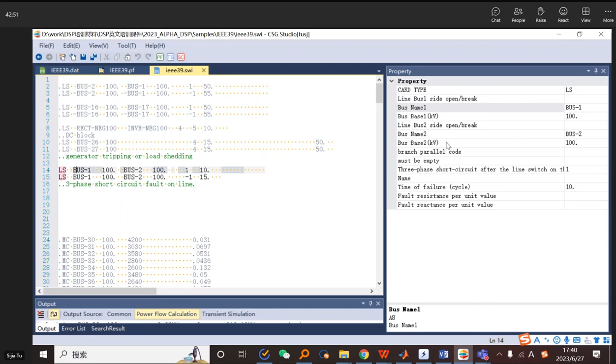For example, one option is a 3-phase short circuit fault. This parameter means the times of failure, meaning what time the failure begins and what time the fault is set. The unit is cycle. If the frequency of the whole system is 50, one cycle equals 20 milliseconds.